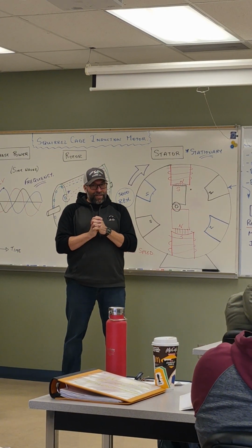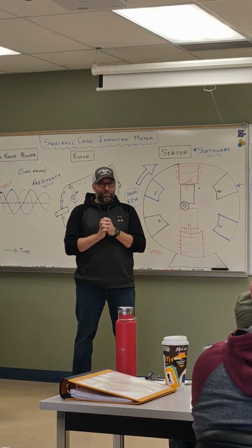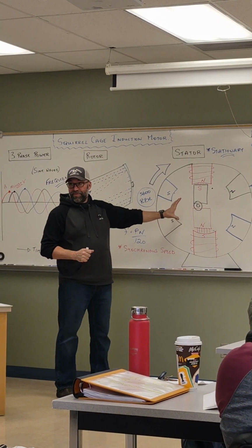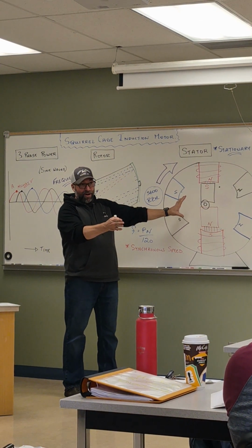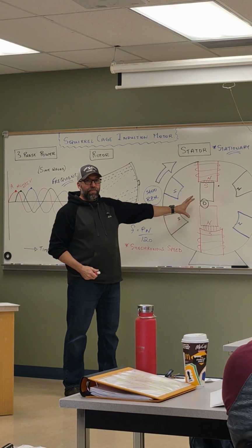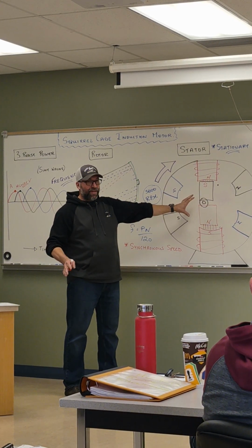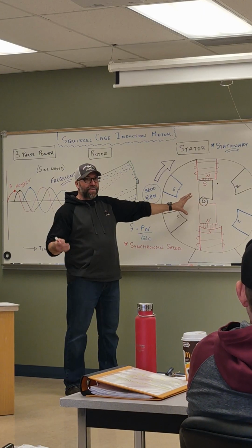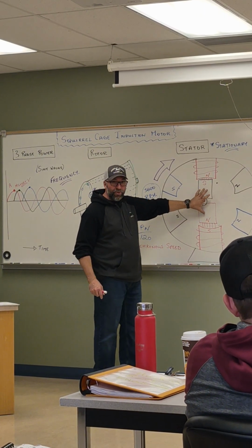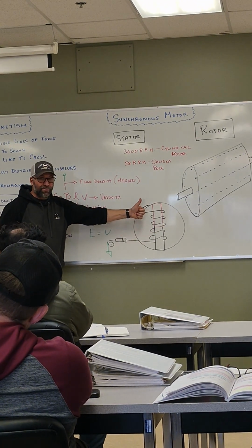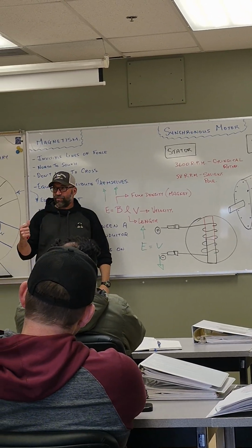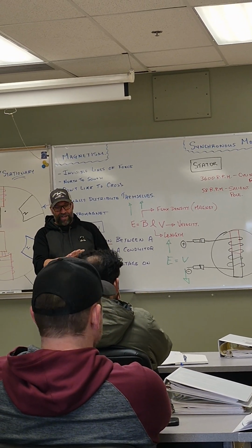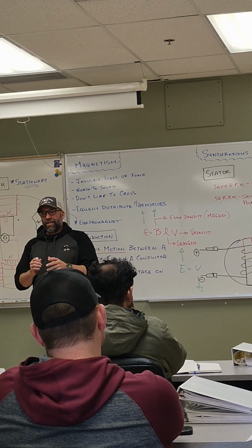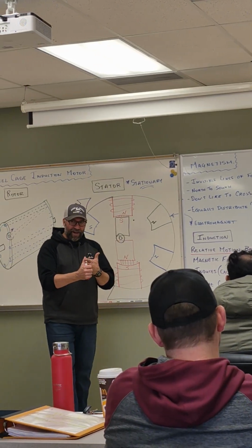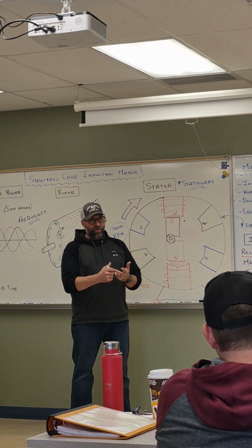Now I'm gonna show you something really quick, because none of my electricians know this until I draw it for them. That synchronous motor is ultra cool. You're gonna get going on power factor. This machine is capable of correcting its own power factor, once you get to it. It corrects its own power factor based on the amount of current you put through the rotor windings. So this right here, that's the rotor windings. As I increase current through that, I change the power factor of this motor. You haven't done power factor yet, right? Today, really cool, this machine does two jobs. It corrects power factor, which you're gonna see is very important, and also drives a load at the same time.